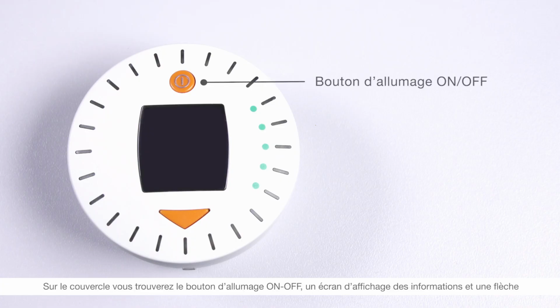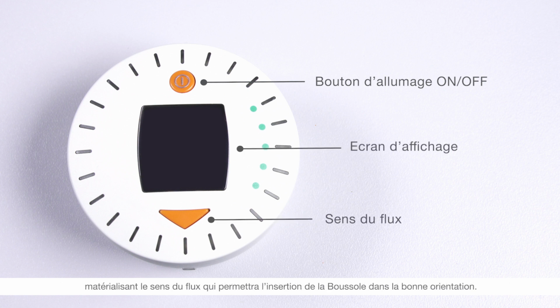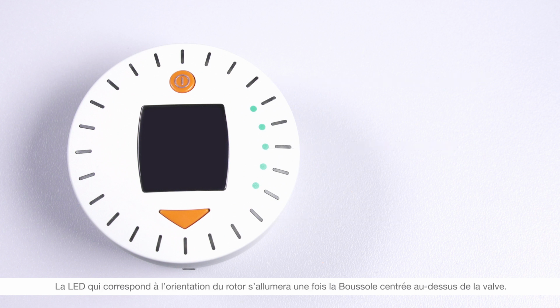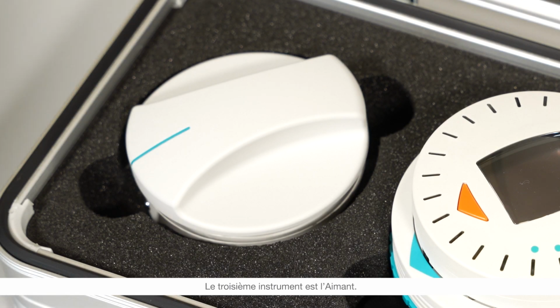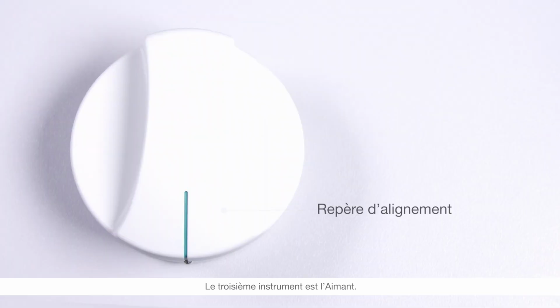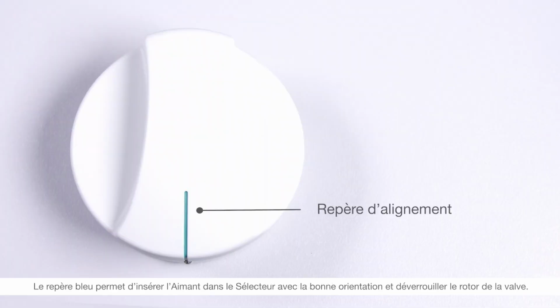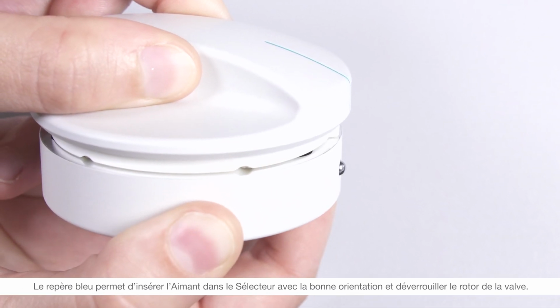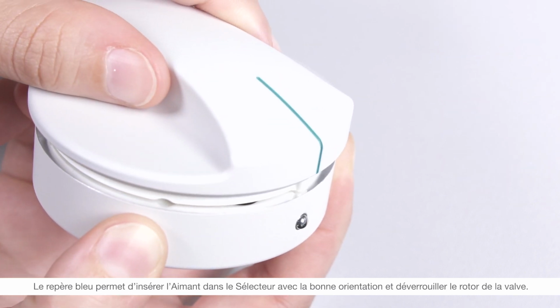On top of the compass, you will find an on-off button, a display screen, and an arrow illustrating the flow direction to confirm that the compass is correctly inserted into the locator. Once the compass is centered, an indicator light on the top of the compass will show the current pressure setting of the valve. The third instrument is the magnet with a blue mark on the handle. It is made up of a specific assembly of magnets designed to allow the unlocking of the rotor and the adjustment of the operating pressure of the valve.